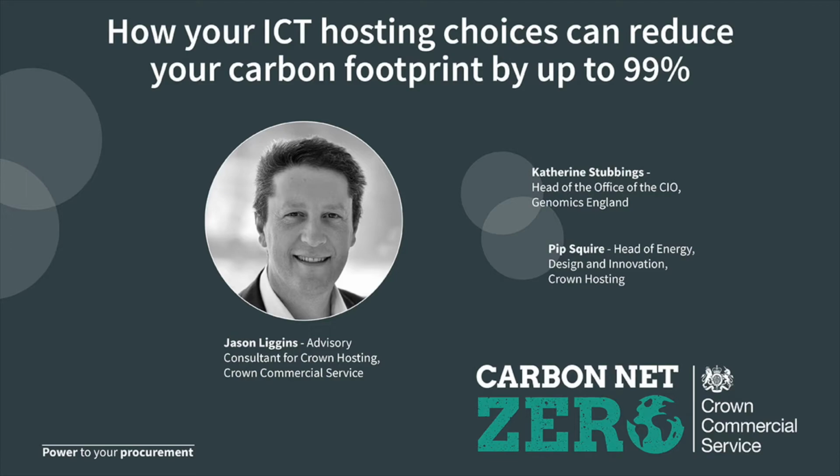We have strict warm and cold zone segregation across the servers, and then we can reuse that warm air created by the servers and mix it with any cold incoming air on cold days. When temperatures are above 25 degrees C, which is not that often in the UK, we'd blow the air straight through without reusing it. We'd also evaporate some water into the airstream because evaporating water, probably the oldest air conditioning system in the world because the Romans used it, can give you about 10 degrees cooling.